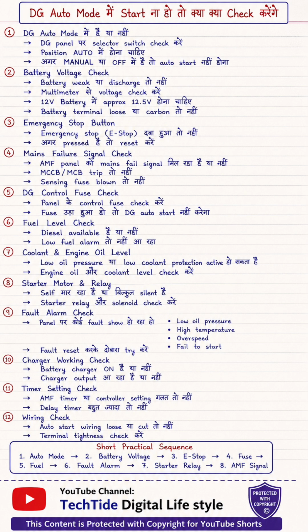Next, check the emergency stop or e-stop button. If the e-stop is pressed, reset it first. Now check the mains failure signal. Make sure the AMF panel is receiving the mains fail signal properly. Also check that the MCCB or MCB is not tripped. And confirm that the sensing fuse is not blown. After that, check the DG control fuse. If the control fuse is blown, the DG will not auto start.